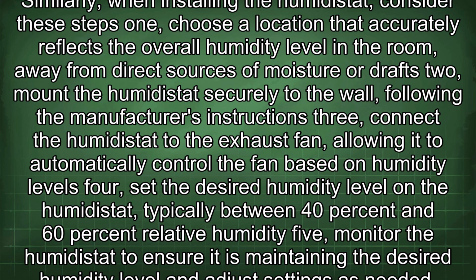Similarly, when installing the humidistat, consider these steps. 1. Choose a location that accurately reflects the overall humidity level in the room, away from direct sources of moisture or drafts. 2. Mount the humidistat securely to the wall, following the manufacturer's instructions. 3. Connect the humidistat to the exhaust fan, allowing it to automatically control the fan based on humidity levels. 4. Set the desired humidity level on the humidistat, typically between 40% and 60% relative humidity. 5. Monitor the humidistat to ensure it is maintaining the desired humidity level and adjust settings as needed.